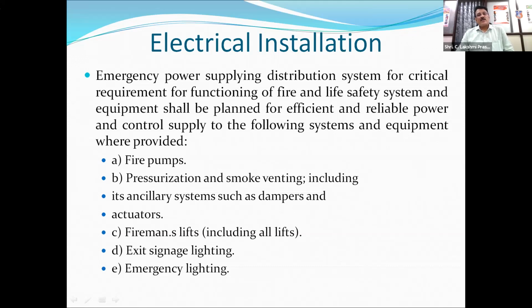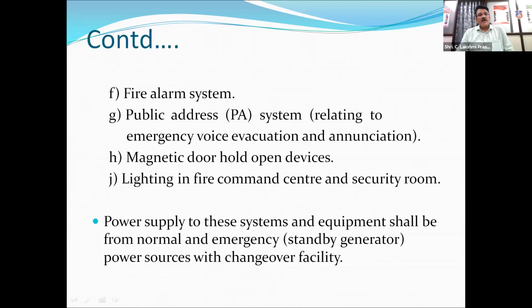So this fire shaft needs to be pressurized. The alternate power supply should be there for pressurization, then fireman lifts, exit signage lighting, emergency lighting, fire alarm system, public address system. Then in many software buildings, there is access control. These access controls have to open the moment the fire alarm goes on, because otherwise people cannot evacuate, they cannot come out.